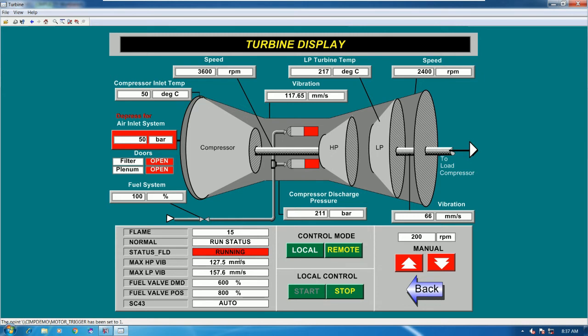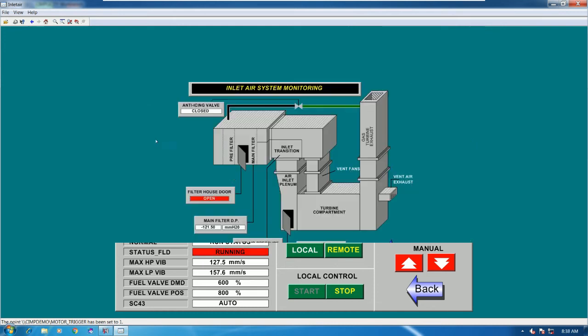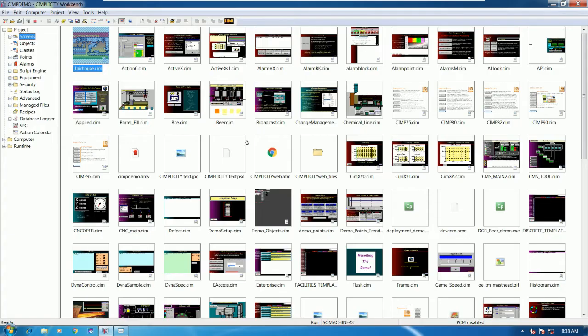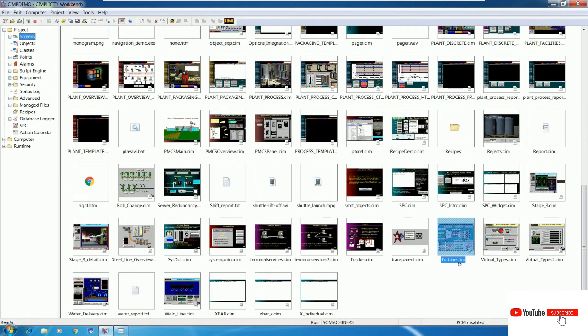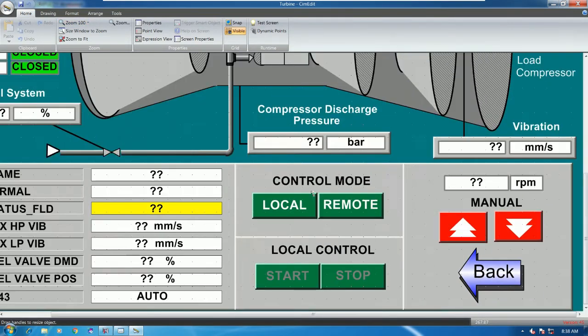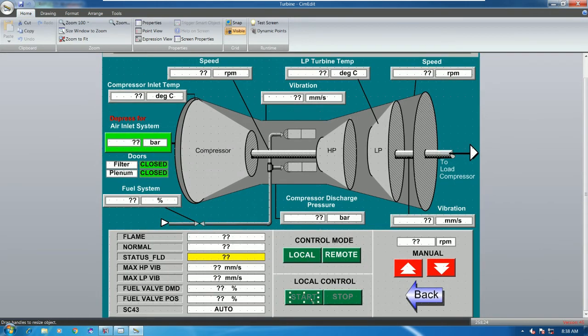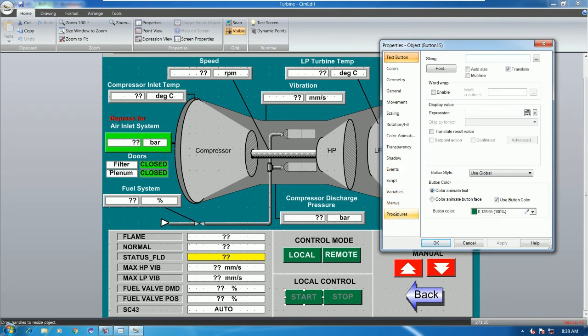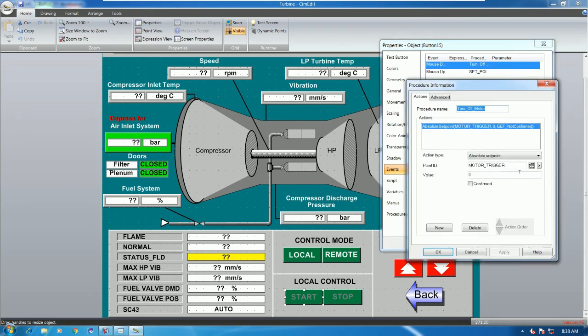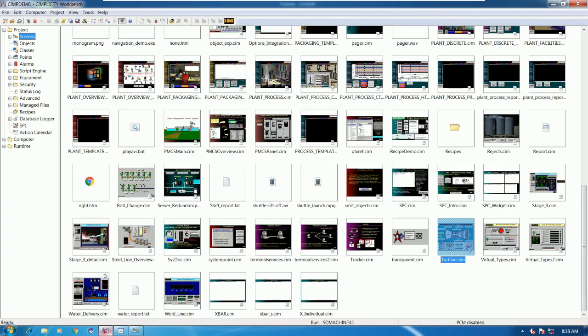Let's see how to configure this button or pressure control. Go to check the screen configuration. Here is the turbine screen — we can edit it and see how it is configured. This button had a confirm action, so let's look at the event. We can see the event to turn off the motor with confirm. Here is the point ID — we can copy this point to search in the points panel.